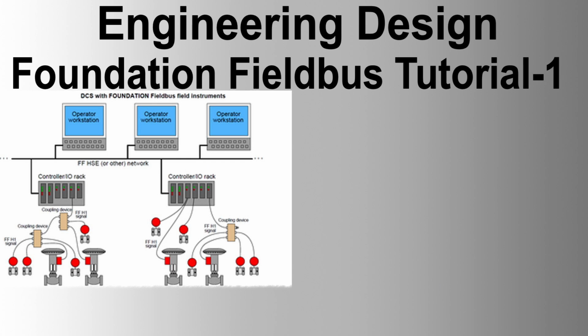A Fieldbus device has many VCRs so that it can communicate with various devices or applications at the same time. It is possible because the VCR guarantees the message goes to the correct partner without risks of losing information. A VCR is identified by an application with a device local identifier called index, specified in the application layer. It is also identified from other devices with DL address specified in the data link layer.